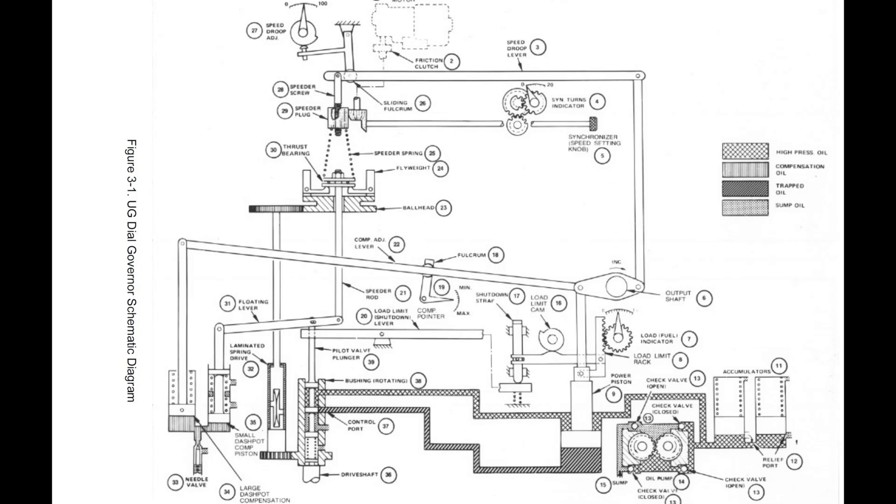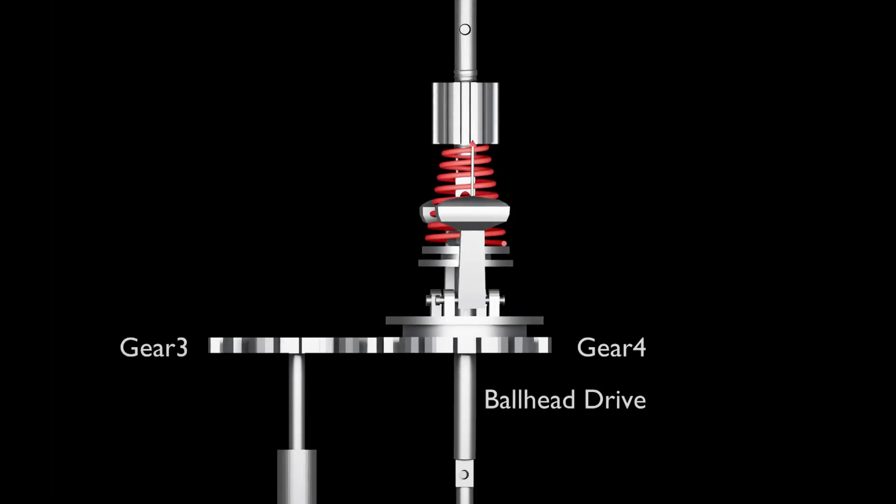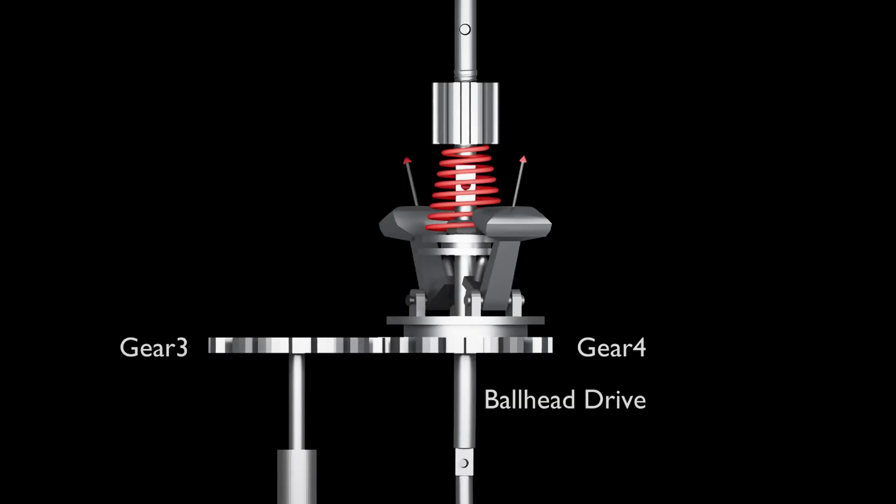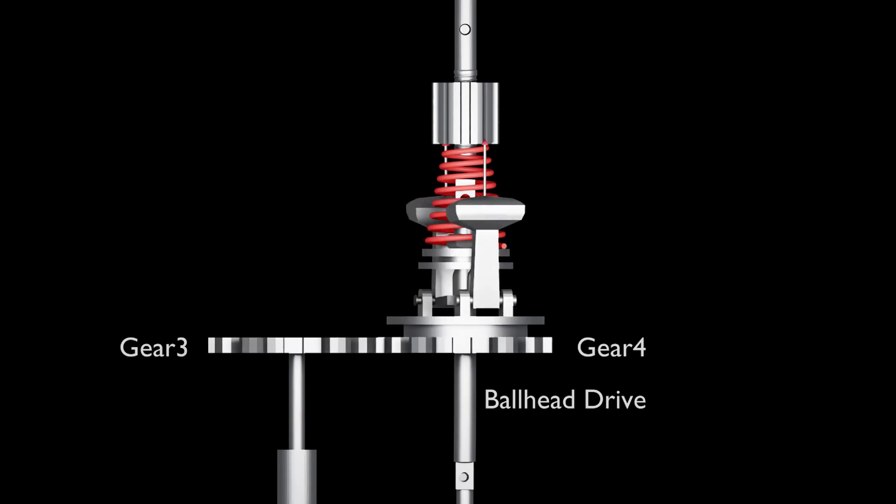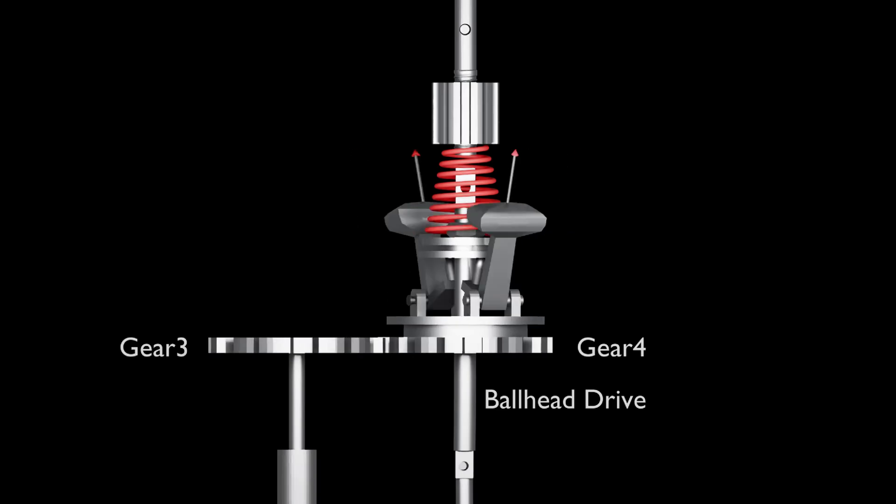Number 1. Speed Sensing Element. These are like the eyes of the governor, always monitoring the engine's speed in real time. These are the starting point of all governor actions. The rotating ball weights are sensing engine speed by rotating at high speed themselves and the centrifugal force that they experience.